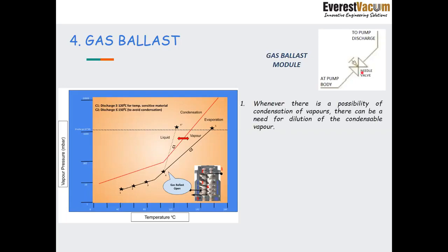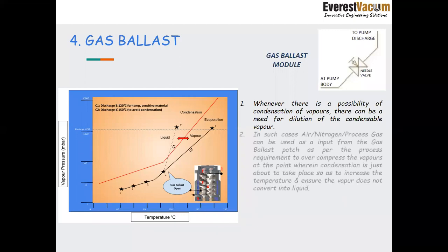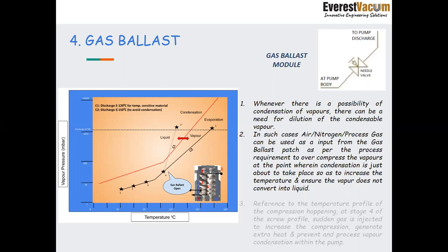So wherever there is a possibility of condensation, we need to ensure that we come up with the gas ballast module. It will dilute the condensable vapors. In such cases, air, nitrogen, or process gas. Now this again depends on the process, what needs to be inserted depending upon the application. It can be an input for the gas ballast, and as per the process requirement, to overcompress the vapors at the point wherein condensation is just about to take place, we inject a small amount of gas. It increases the temperature and ensures that the vapors don't convert into the liquid.